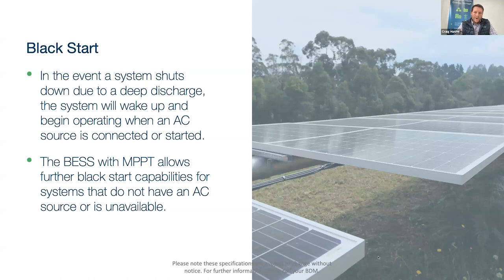A lot of people are used to systems out in remote areas, where when a system goes down it can be a nightmare to get it up and going if you need to travel to site. The product has what we class as a black start capability built in. Should the batteries have a deep discharge, which can happen especially in blackout situations, and the batteries go to sleep, simply plugging in a generator and starting, or turning the grid on, or when the sun comes up if you've got a DC coupled version of our products, it'll automatically wake the batteries up and the system starts charging and powering. So it takes the onus out of some of the management side of the system.